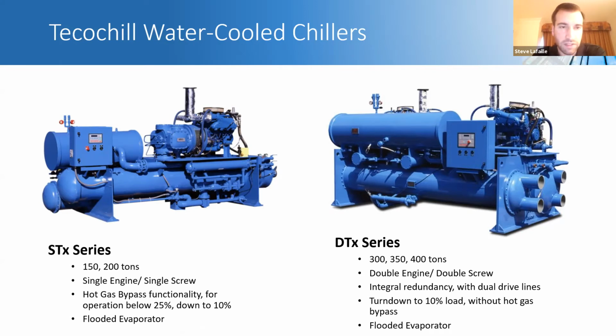What's really interesting is that this is a VFD screw chiller. We've had a VFD screw chiller for 30 years. So the engine is the VFD, it's just a mechanical VFD. We essentially have the gas pedal, right? So when we want to change load, we're just adjusting engine speed, which in turn adjusts compressor speed. It's the most efficient way to control load and load follow.